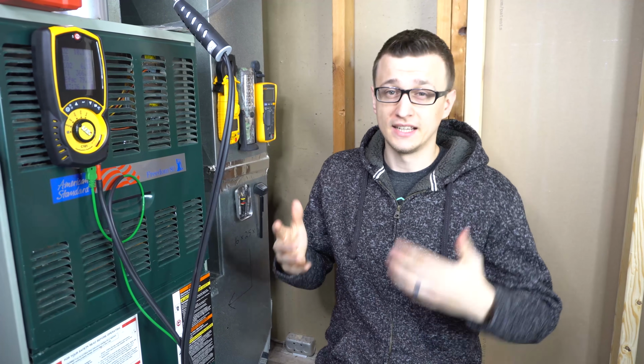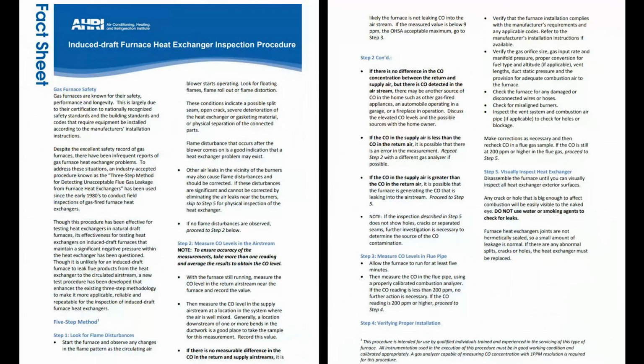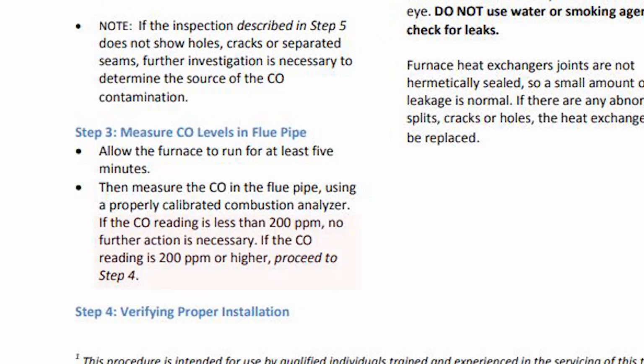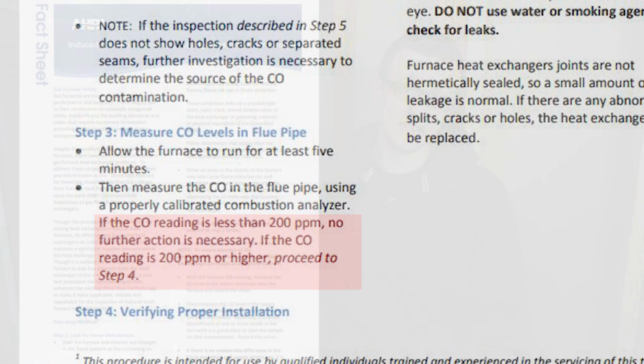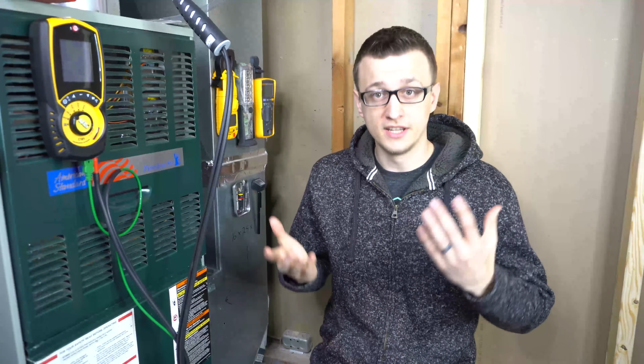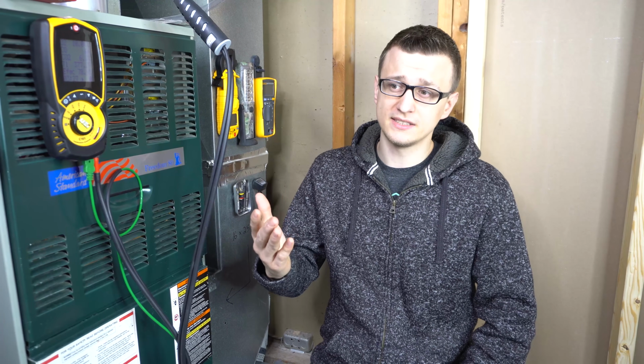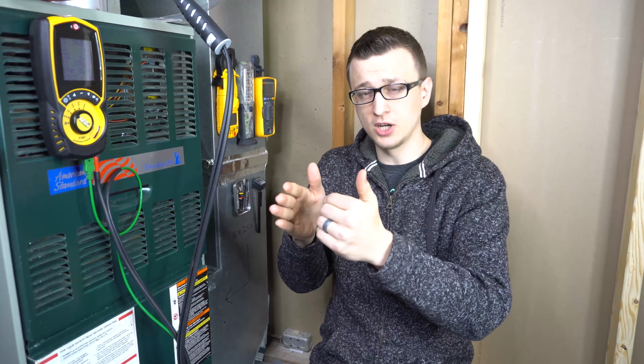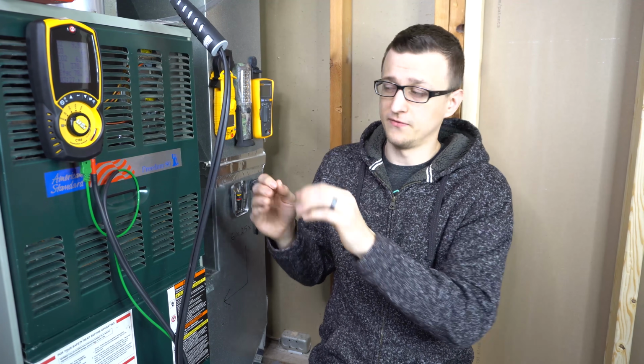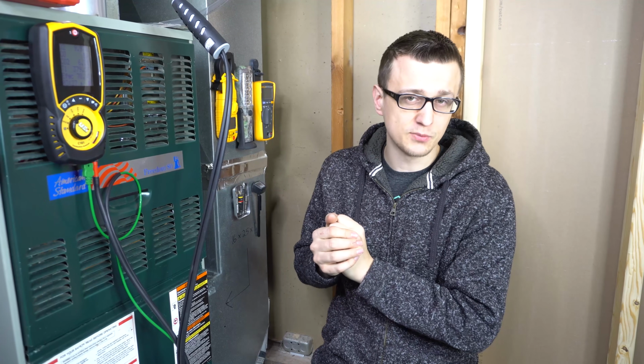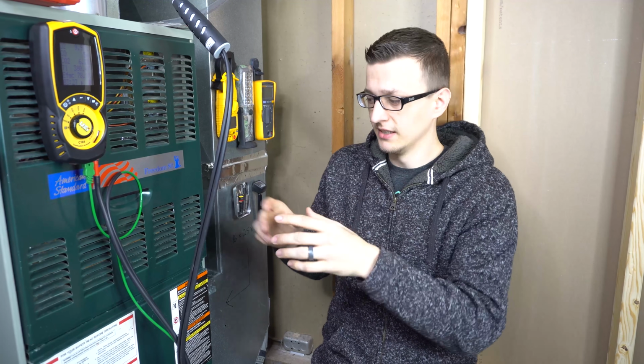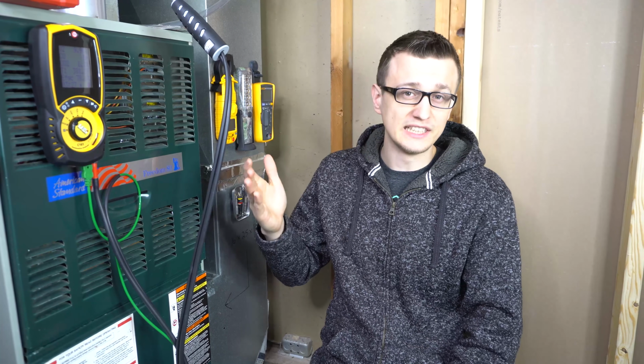So what is the allowable carbon monoxide levels going out the furnace flue? And the answer to that is, according to AHRI, if the carbon monoxide emissions are 200 parts per million or lower, no further action is needed. So anything under 200 is acceptable. Most companies, if the carbon monoxide gets to 100 parts per million, we would do a little bit further investigation, maybe check the gas pressures, make sure there's enough intake air, check the burner restrictors, see if anything's going on there, maybe clean the burners.